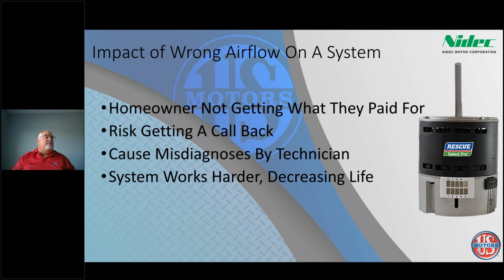Homeowners aren't getting what they pay for. If you take it out and put a PSC in there, you're taking away all that efficiency. There's the risk of a callback because it's not heating or cooling like it used to, and they will notice. Then there's misdiagnosis by the next technician, say they put in the wrong motor or didn't program it right. It'll be hard for them to understand what was going on with the system. And of course, you cause the system to work harder, decreasing the life expectancy of the entire system.